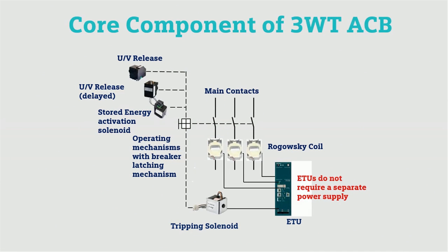The core components of the 3WT ACB include an electronic trip unit which receives current sensing from a robust Rogowski coil. It also has a tripping solenoid connected to the operating mechanism with breaking and latching functions, an undervoltage release coil, an undervoltage delayed release coil, and a stored energy activation solenoid.